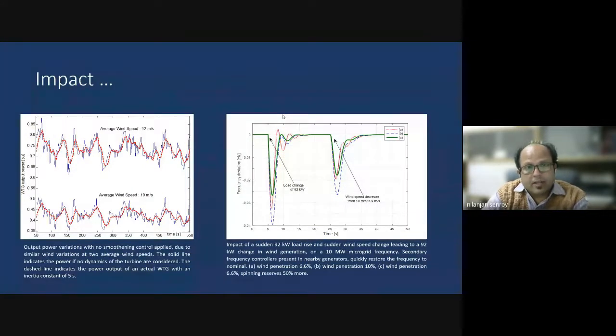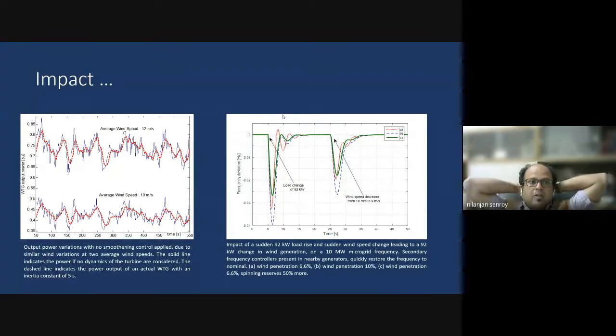Another thing that has been observed is the active power deviation because of wind speed deviation. If you have a wind turbine of significant inertia and the wind is varying continuously, then the active power output also varies. However, there is a certain amount of smoothing by virtue of the shaft inertia, even if you do not apply any artificial controller to smoothen out the fluctuations. The blue curve refers to wind variation and the red curve refers to the output active power variation. You can see there is a certain amount of smoothing. This smoothing is different at different wind speeds.